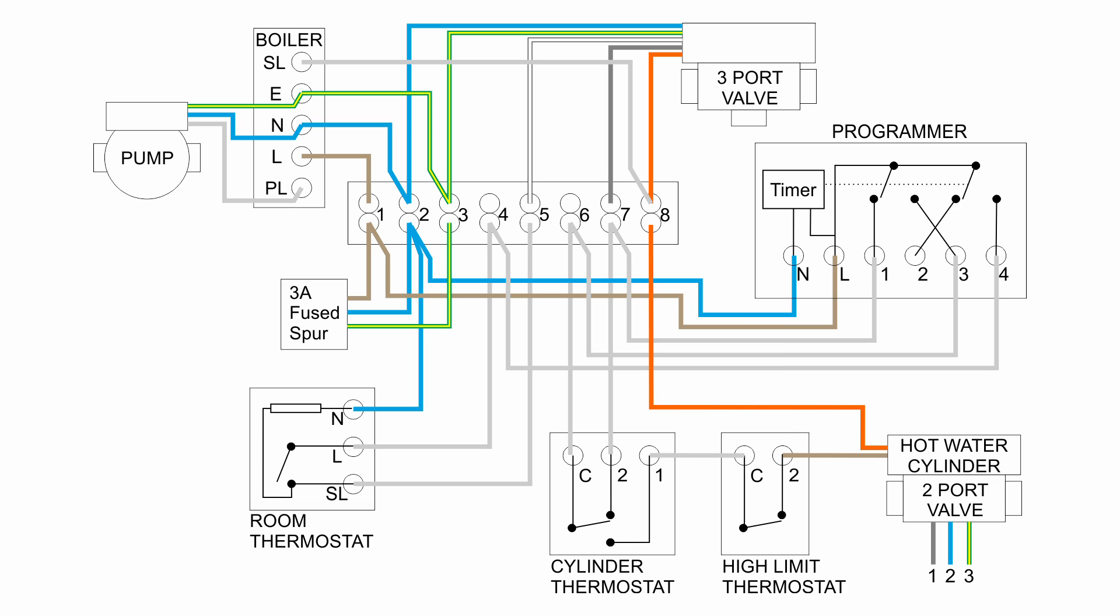And crucially, unlike the other type of thermostat, once this has opened it doesn't reset automatically, so essentially if the cylinder gets too hot and this thing opens, it will stay open until someone actually goes in and manually resets the thing. And this is an important safety feature, so that if something does go wrong, it's not just a question of it then returning to normal operation later, someone has to actually go in there and at least reset the thing manually, and ideally find out why it overheated in the first place.